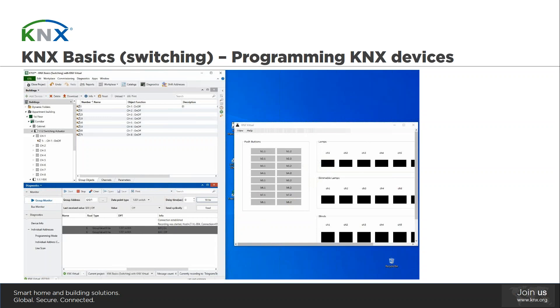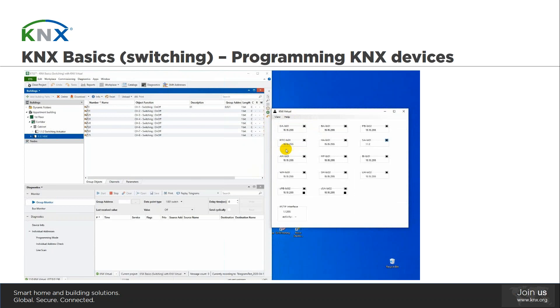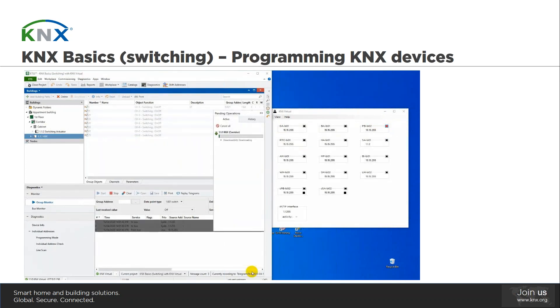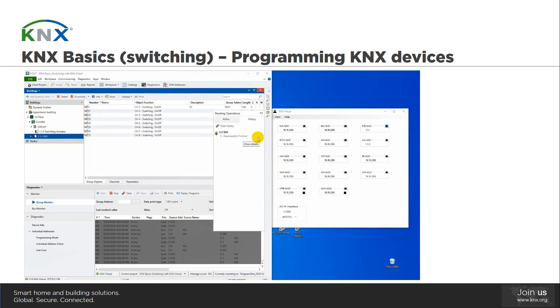Congratulations, we have a first function in KNX, although it's not yet complete. Let's complete it. We wanted to have this function operated via the push button. One more thing to do is to also program this device with a full download. We go to the Devices view, activate the programming mode of the push button, and trigger a full download from ETS. The individual address of the push button is assigned and the application program is being downloaded.